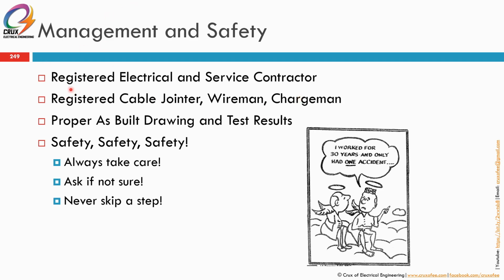So there must be a valid and registered service contractor and service electrical competent person. And make sure you have proper as-built drawing and test results. These are all proofs that you, or the electrical contractor, or you as a project engineer, have done the commissioning work up to the standard and as accepted by the regulation. And finally, from the very beginning, always emphasize on safety, safety and safety. Always take care, not yourself only, but also others who are working.